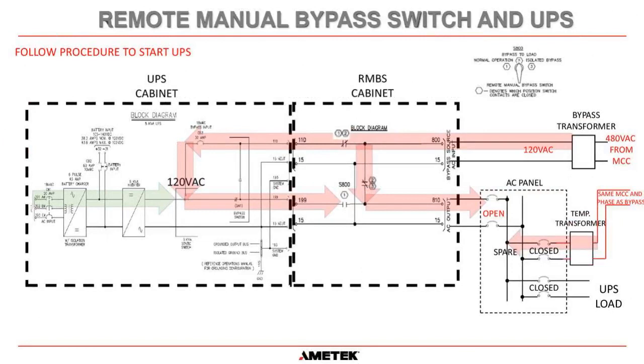And then we follow the procedure to start up the UPS, okay? So we energize the UPS, the charger is now on, the inverter is now on, and we have power going to the static switch. Once again, I don't know why that line's disappeared because it's actually on my presentation. So we do have power going there, but we're in the bypass to load on the static switch, remember, because this switch is always going to be closed here on UPS.